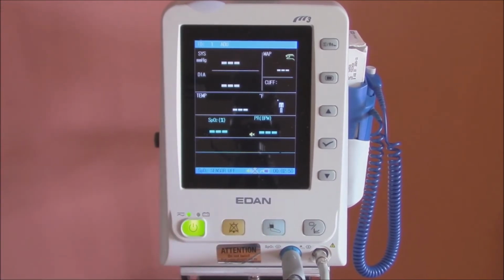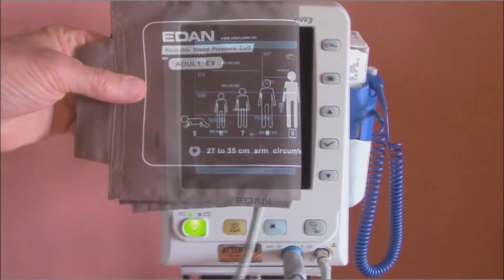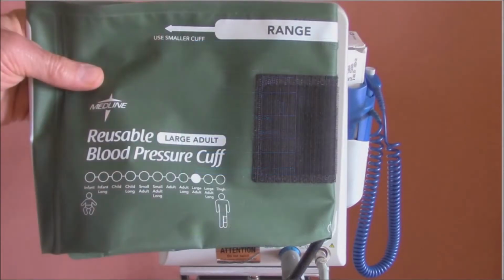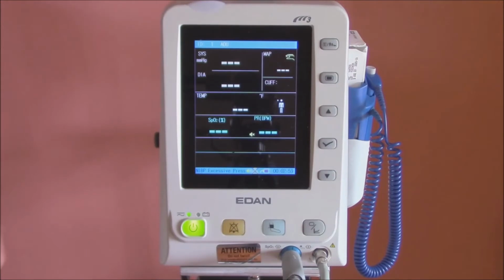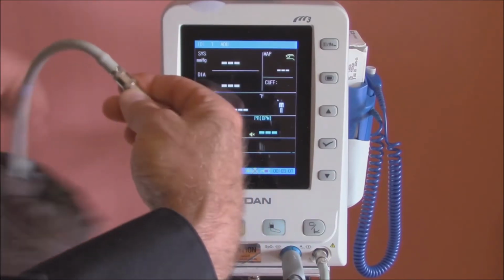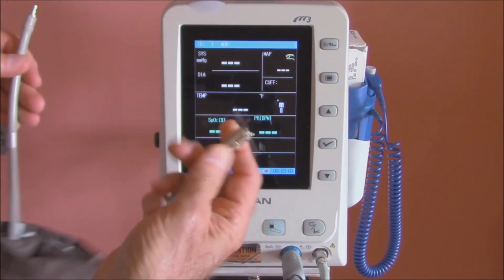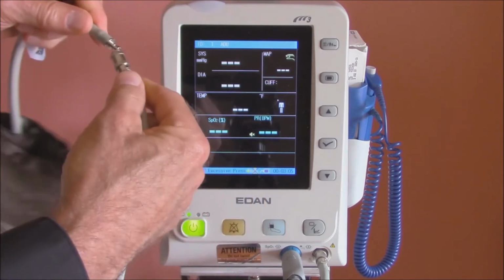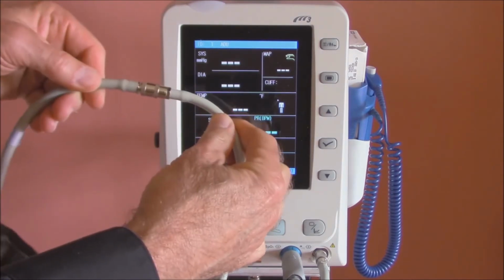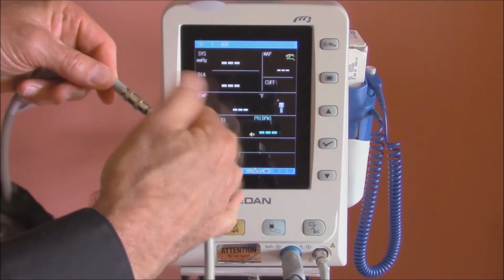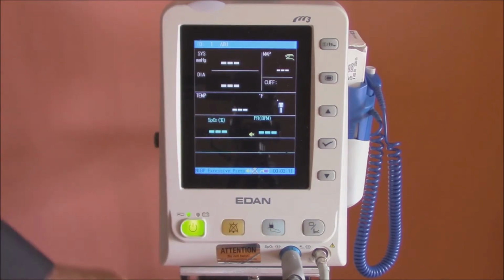The Vital System comes supplied with 3 blood pressure cuffs: Adult Small, Adult, and Adult Large. To change the blood pressure cuff, simply pull back on the spring-loaded connection ring on the blood pressure hose and the cuff will release. Insert the new cuff by pressing the fitting into the hose until it clicks in place. Please do not twist the connection ring, as this will eventually break the spring inside the ring.